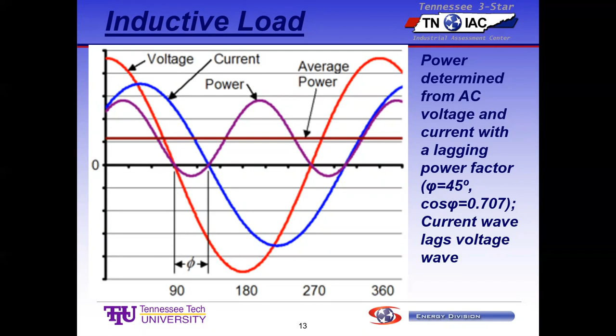However, in a circuit with a bunch of inductance, the current is lagging behind the voltage. The voltage peaks over here, but the current doesn't peak till later. The voltage crosses zero here, but the current crosses zero here. So this is a phase shift, and in angular terms that's theta. The power factor angle is the phase shift between those two. So this is the problem: the inductance feeds in magnetizing energy in a positive sense, but then as the wave starts to collapse, that energy goes back into the circuit and it retards the current waveform. If you want to get into the physics of it, that's what causes this effect.